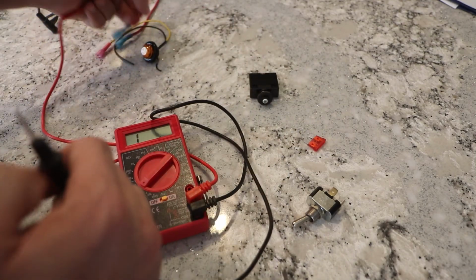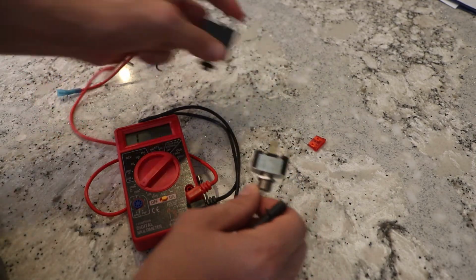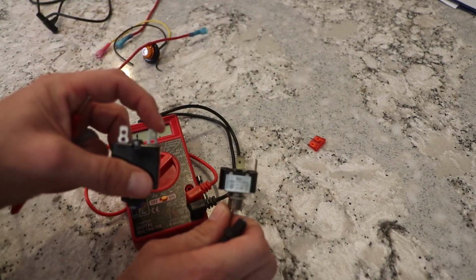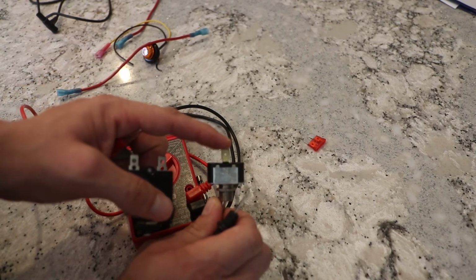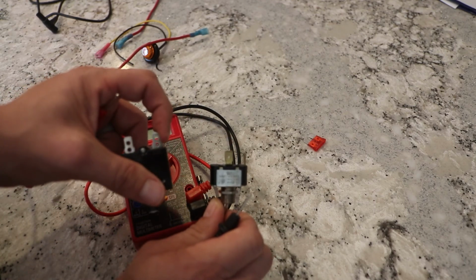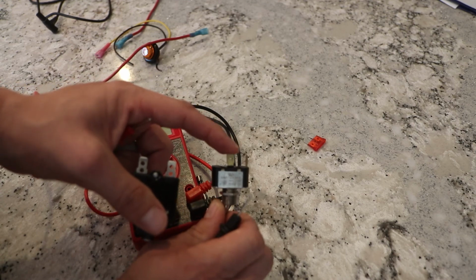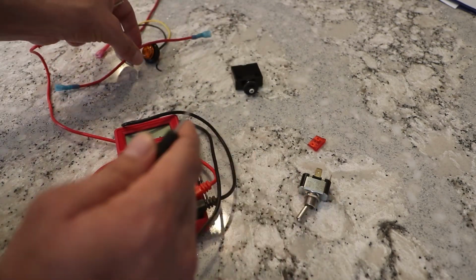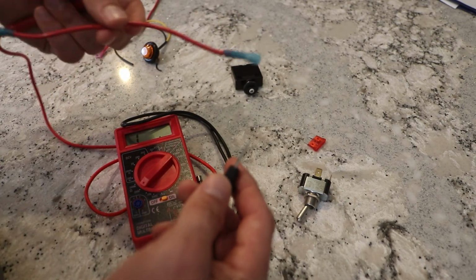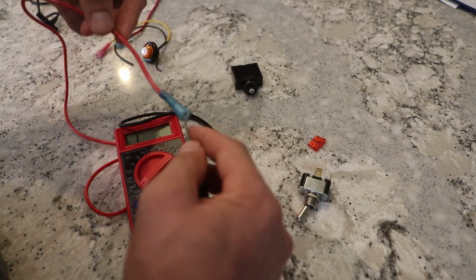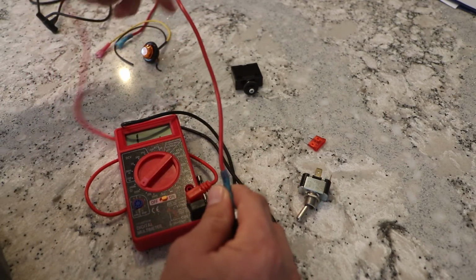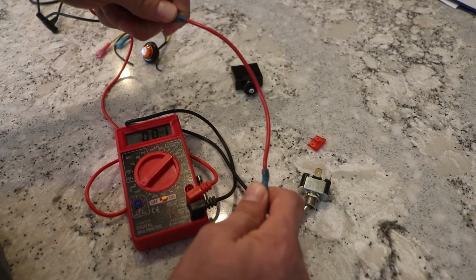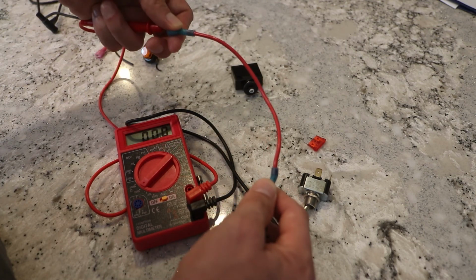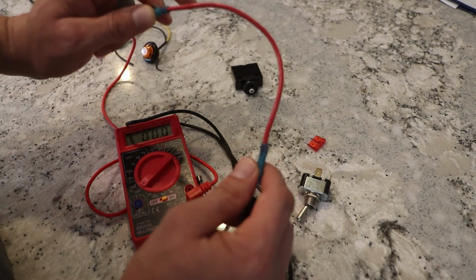Next, let's say between the circuit breaker's downstream feed and the incoming on the switch, you're getting 12 volts here but not here. You test what's in the middle just like you test any of the switches or circuit breakers. So you test the wire and connect both ends, and you can see here I have no resistance at all, which tells me this wire is good.